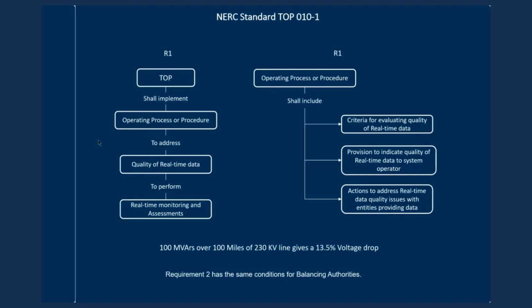Well, the rule of 100 megavars over 100 miles of 230 kV line gives a 13.5% voltage drop can be applied to real-time networks and validate that, given the megavars traveling over a certain path, by figuring out the distance of that path in equivalent 230 kV line length, you can verify whether the voltage at the sending end and the receiving end is reasonable.